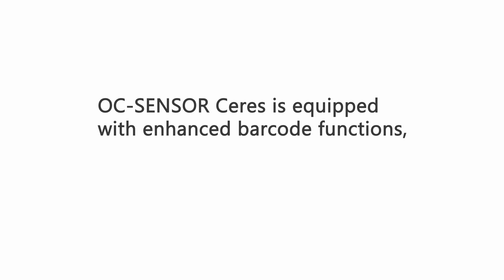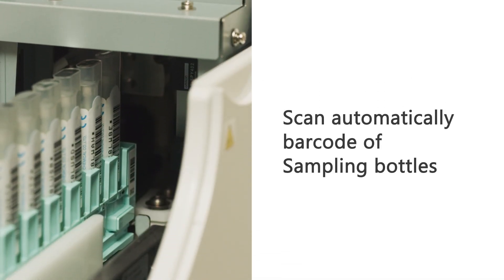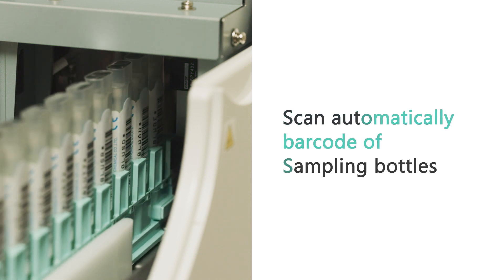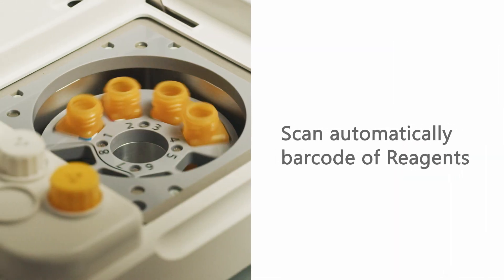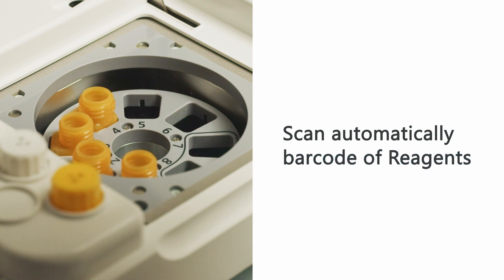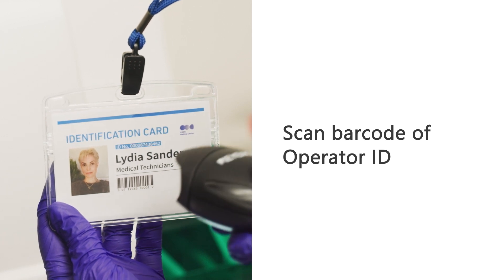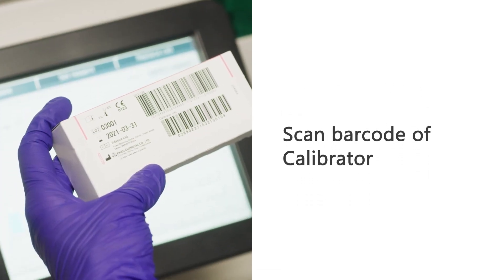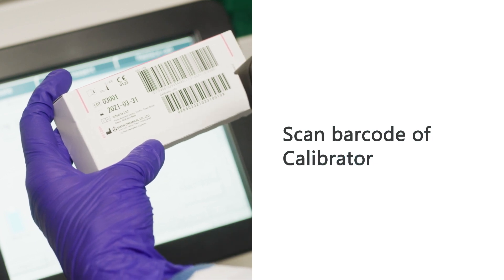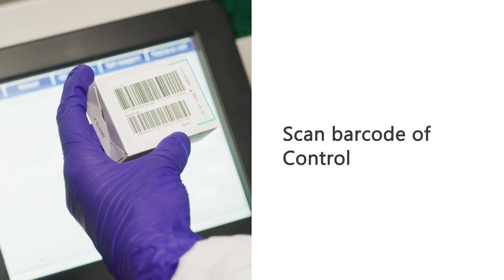OC-SENSOR Ceres is also equipped with enhanced barcode functions, making it easier to conform to ISO 15189 standards. Patient IDs on sampling bottles are scanned automatically when the sample rack is placed, and reagent information is scanned automatically when the reagent bottle is set in place. The optional portable barcode reader saves time and helps reduce human errors when entering information for quality control, including operator ID, calibrator lot number, expiration date, test parameters, control lot, and reference range.